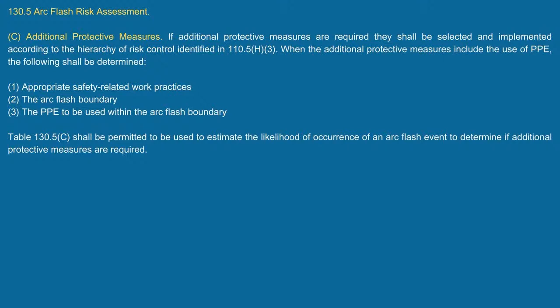I agree. Now, let's look at C1 first, appropriate safety-related work practices. If you remember last week, I was talking about the shock protection boundary and the limited approach boundary, and I said sometimes you have a safety backup when somebody's working inside that limited approach boundary. But let's say they're inside the arc flash boundary. If something happens to that person while they're in there, how are you going to handle this? Well, I may have a disconnect inside that boundary. Then what I'd want is a non-conductive pole. If something happens, I can take that pole and hit the handle of that disconnect and turn it off.